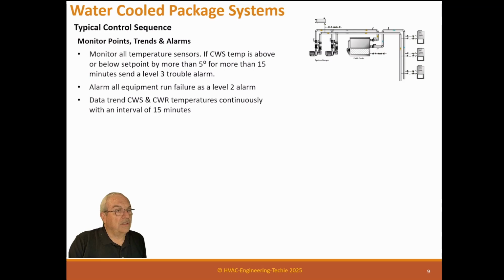Data trend condenser water supply and condenser water return temperature continuously with an interval of 15 minutes. So every 15 minutes, we're going to data log where the supply and return is on this condenser water. So an operator can bring that up and look and say, well, here's what we're doing. We're doing pretty good. Or, boy, something's going wrong. We need to check this out. So since it's every 15 minutes, it's only 4 points an hour.